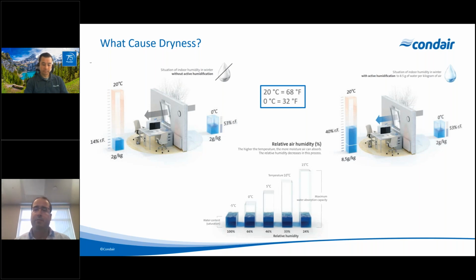If you increase your relative humidity, that difference becomes lower and lower, and the tendency to release moisture is much lower. You can see at the bottom what happens when you increase temperature while keeping the same absolute humidity, your relative humidity will drop. So what we want to do when humidifying, whether for health or for processes, is also increase absolute humidity to keep a constant relative humidity.